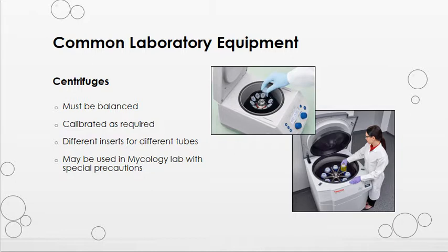Common lab equipment found in almost every department in the lab includes centrifuges, refrigerators and freezers, microscopes, biosafety cabinets or fume hoods, and so on. Centrifuges can be small, large, or any size in between. They must be balanced when in use, and they are calibrated and cleaned regularly. Some centrifuges have different inserts that can be changed depending on the tube type being used. Centrifuges are used in most departments in the lab, and they can also be used in mycology as long as special aerosol precautions are taken.